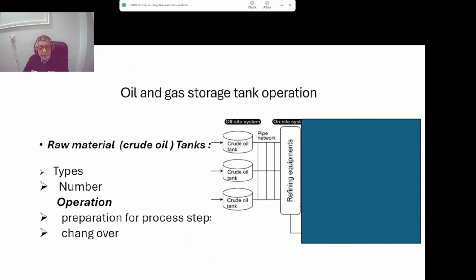After receiving the quantity, leave at least 1 meter height empty at the top, then send the product to the other tank and close the inlet of the first tank, which was for receiving, and make the second tank for receiving. The first tank is left for at least 10 hours to settle down. After settling, we make a drainage to remove the water which has settled at the bottom of the tank. Then make agitation, and after agitation take the sample. The sample is 3 samples, from the top, middle, and bottom of the tank.